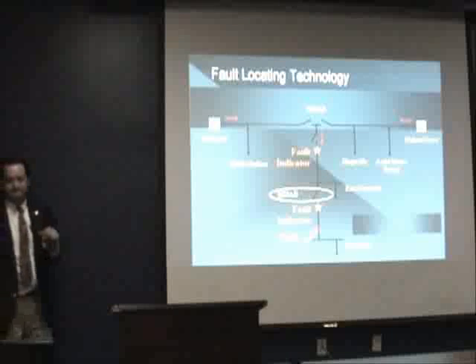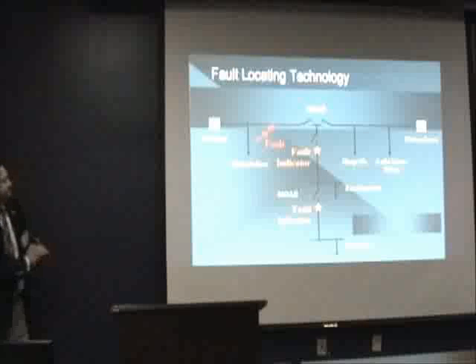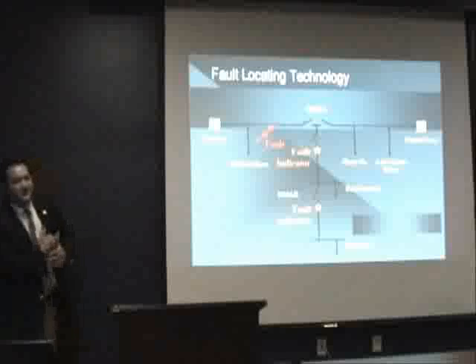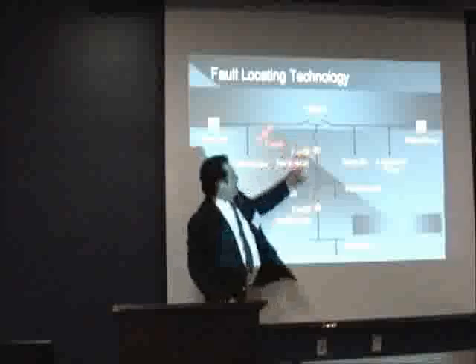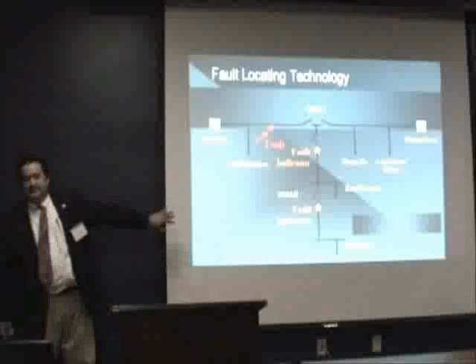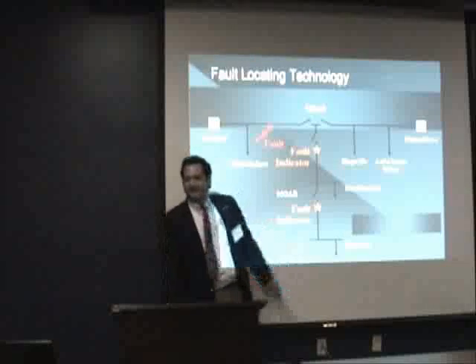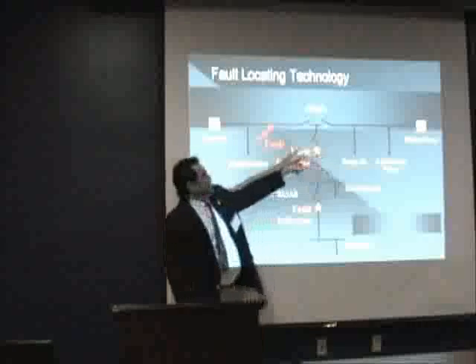All right? What if the power line problem is over here? Well, this guy didn't see it, and this guy didn't see it. But that's still valuable information to the dispatcher, right? Why? Because he knows that he can either get power to this guy or power from this guy, and these guys are still going to be in good shape. So don't just assume that I need to open this and get rid of these guys. I've just told you that there's no problem here. So first I'm going to open that, and I'm going to close that one in, and close that one in.